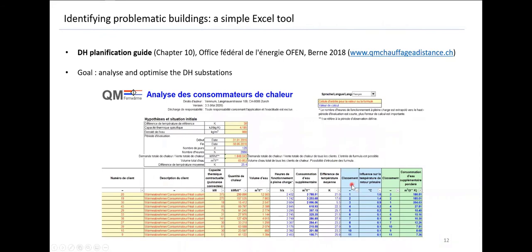Before presenting this tool, I should mention that more sophisticated methods exist relying on daily data to detect faults more quickly. But this tool has the advantage that it is free — you can download it at the given address — it works with Excel, and it requires only a very few data points to make a ranking of your substations.